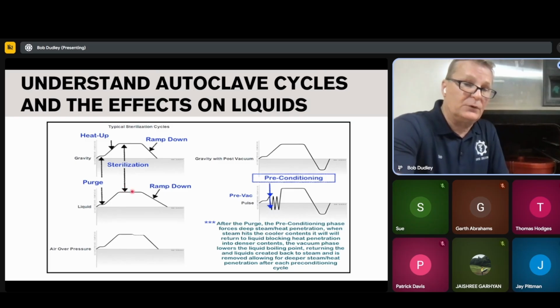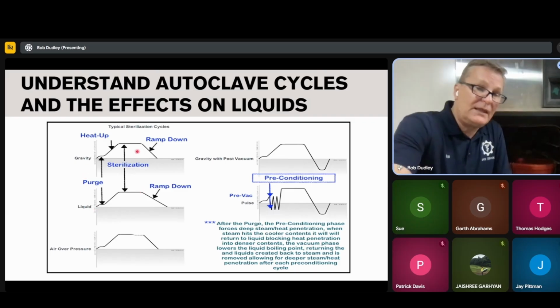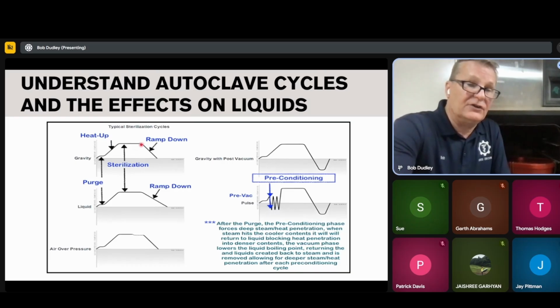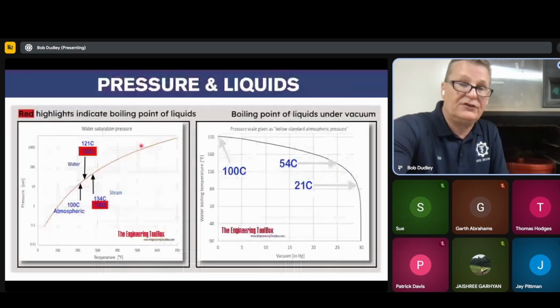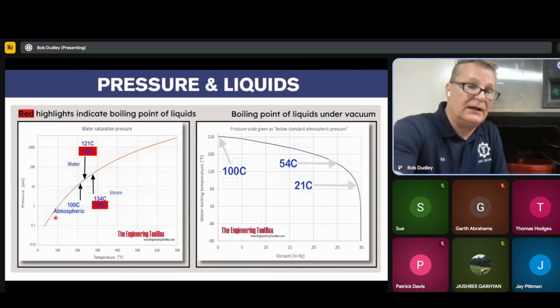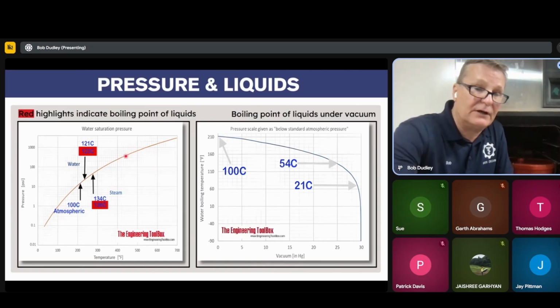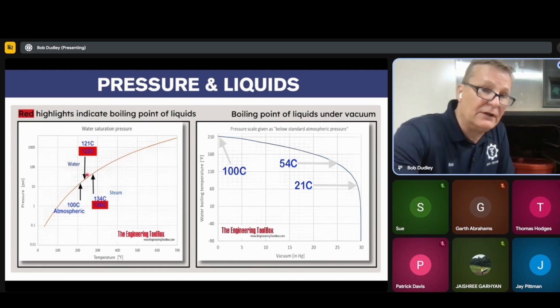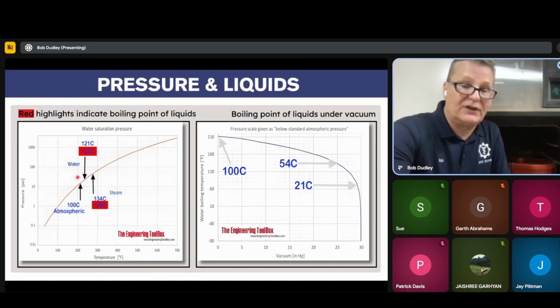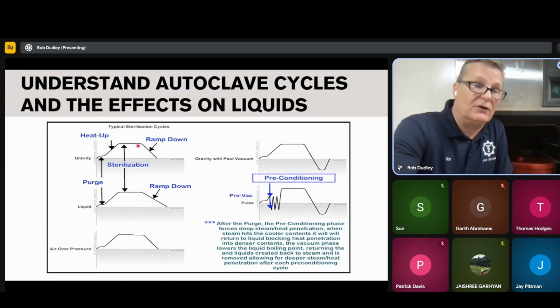But if it's successful, you're going to run the amount of time that you're going to run, and then the ramp down. Now, the difference between the gravity and the liquid is the ramp down. And going back to this chart here, where you have the pressure and the temperature of it and the boiling point. So if you're here at 121 and your boiling point is here, and then you suddenly drop here, but that temperature remains the same, what you've just created is a volcano.